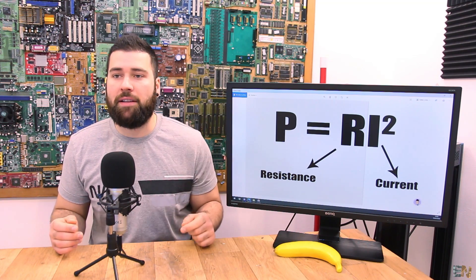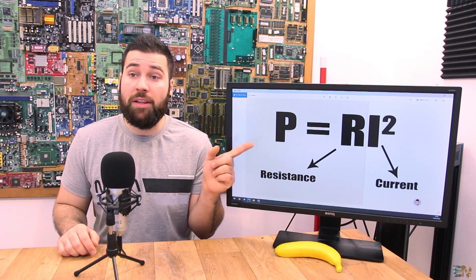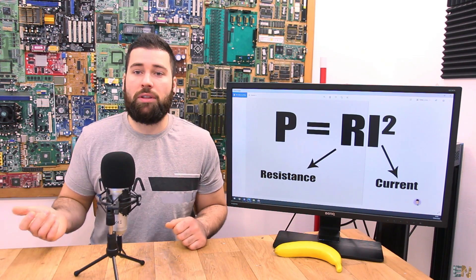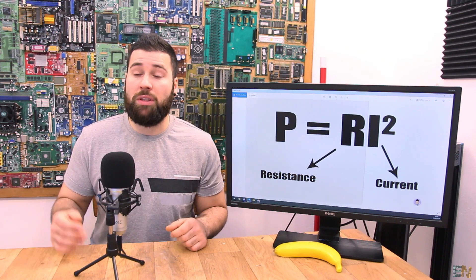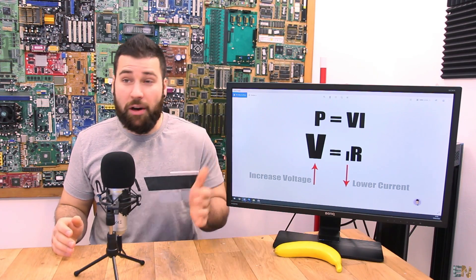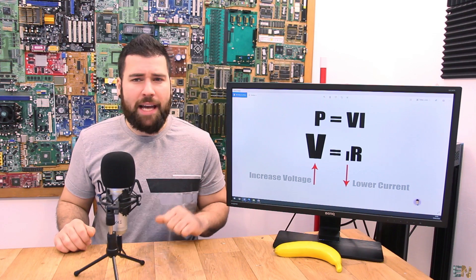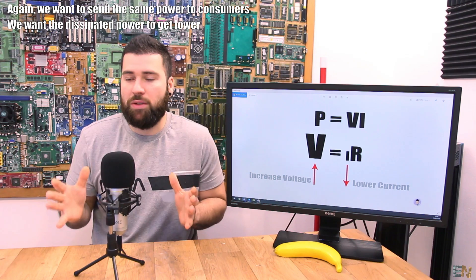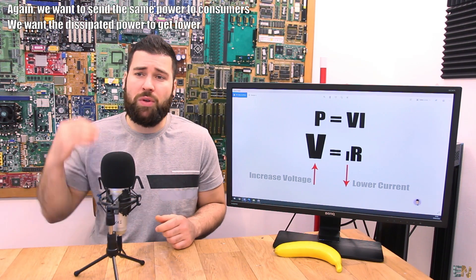The problem is in the squared factor. If I reduce the resistance by half, the power loss also reduces by half. But if I reduce the current by half, the power loss reduces by 4 times because of the squared factor — the power loss reduces on an exponential scale. So the better solution is to lower the current value, not the resistance. To reduce the current while keeping the same resistance and the same power in the lines, we have to increase the voltage significantly. Increasing the voltage is a lot easier than reducing the resistance of the cable.